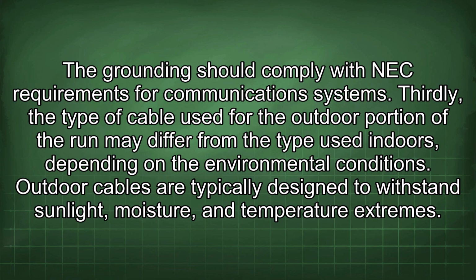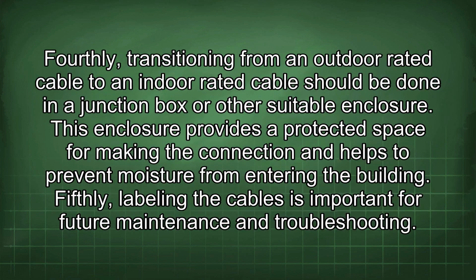Thirdly, the type of cable used for the outdoor portion of the run may differ from the type used indoors, depending on the environmental conditions. Outdoor cables are typically designed to withstand sunlight, moisture, and temperature extremes. Fourthly, transitioning from an outdoor rated cable to an indoor rated cable should be done in a junction box or other suitable enclosure.